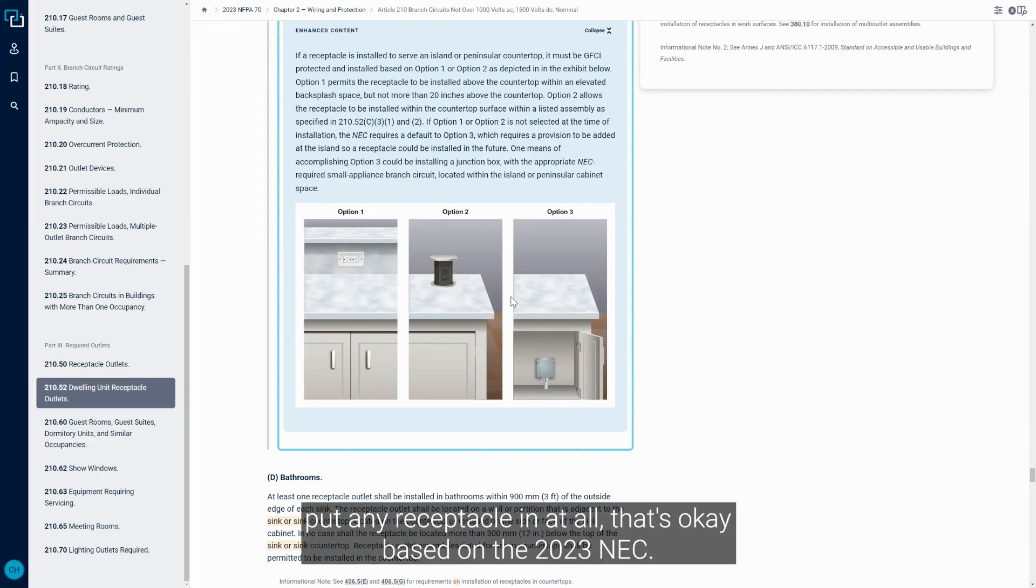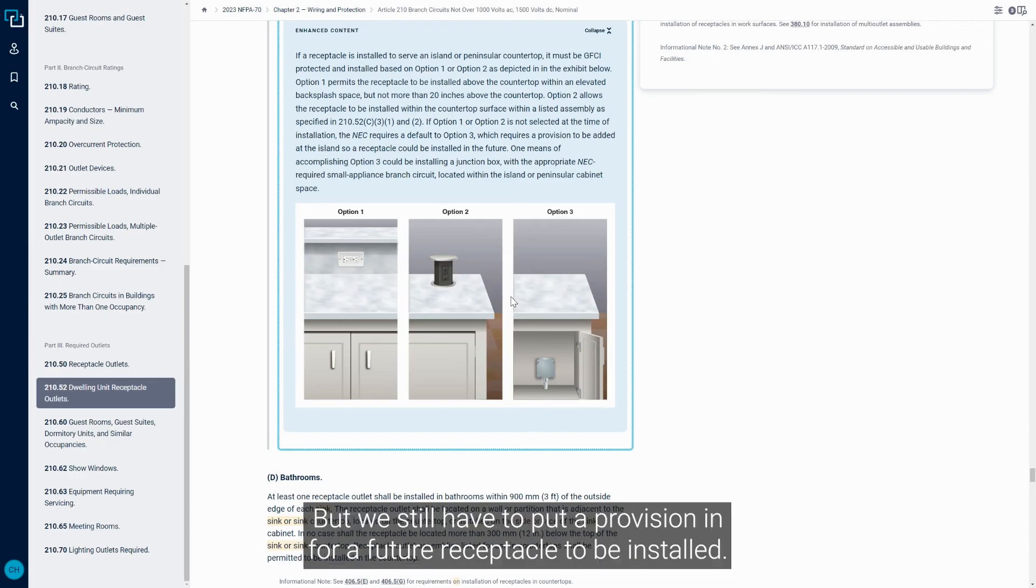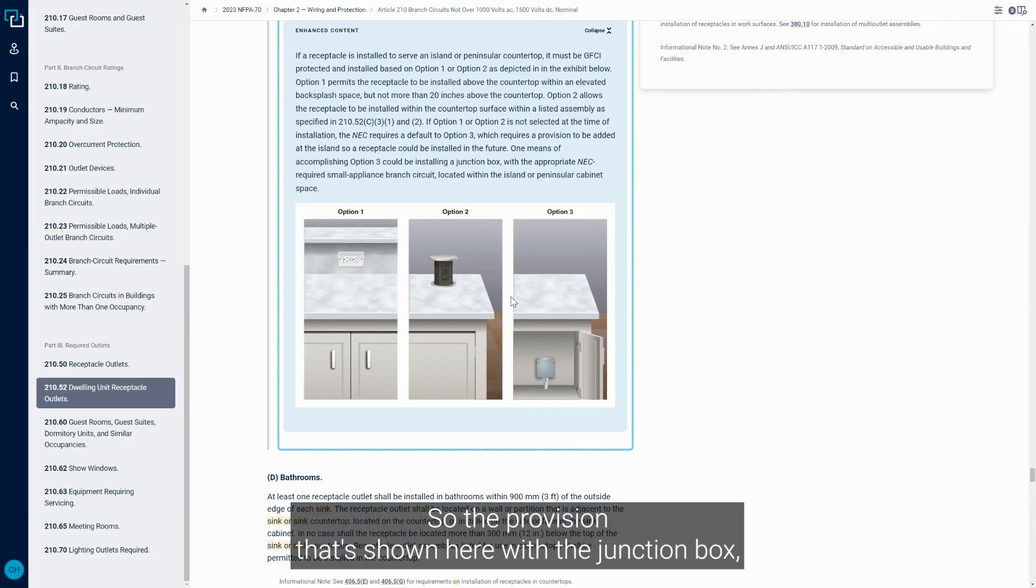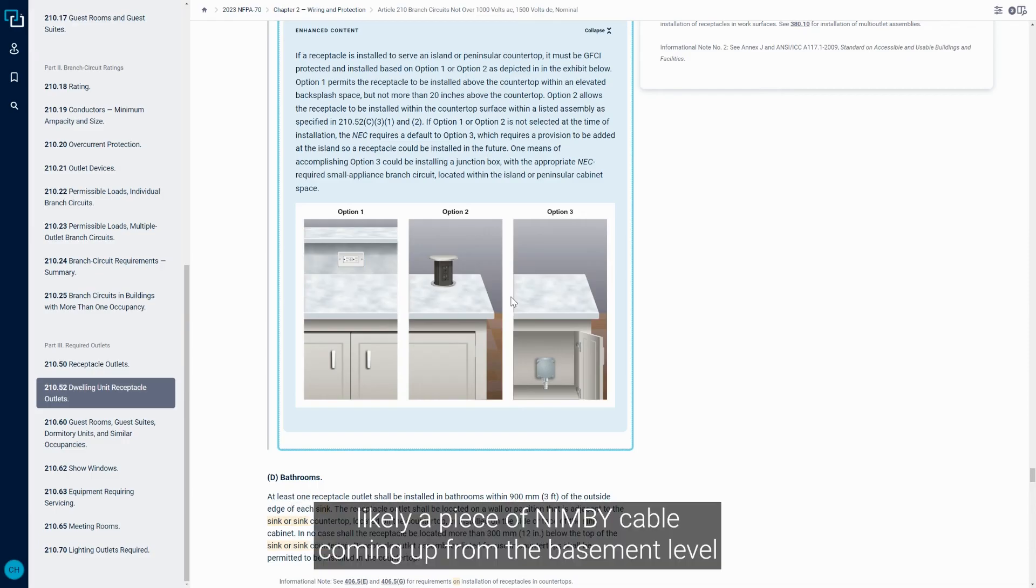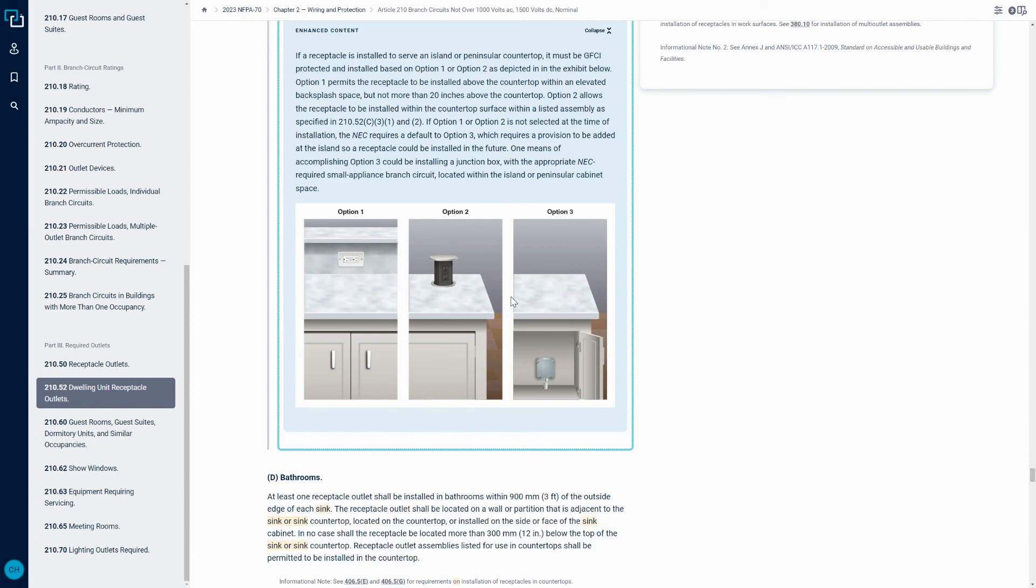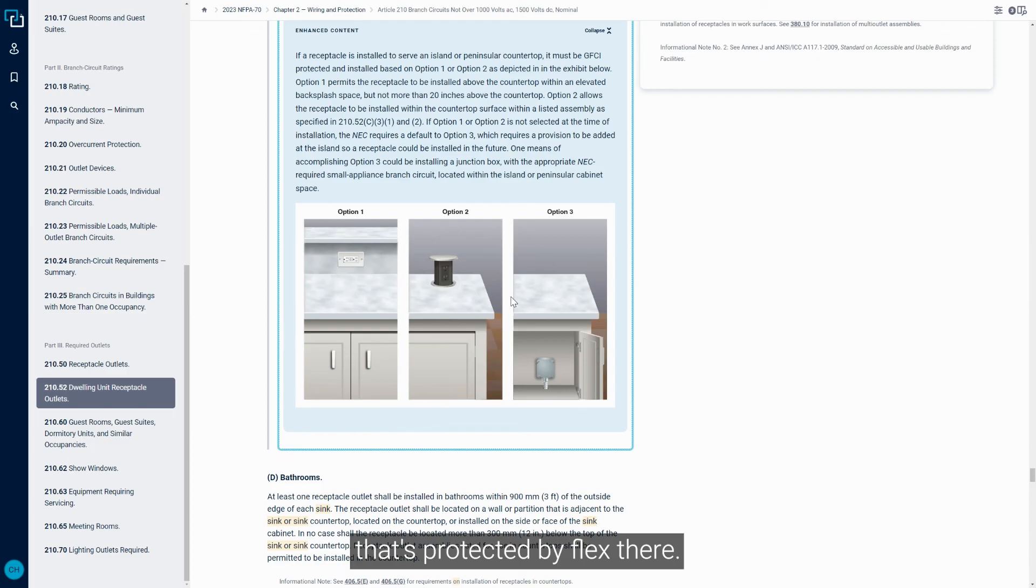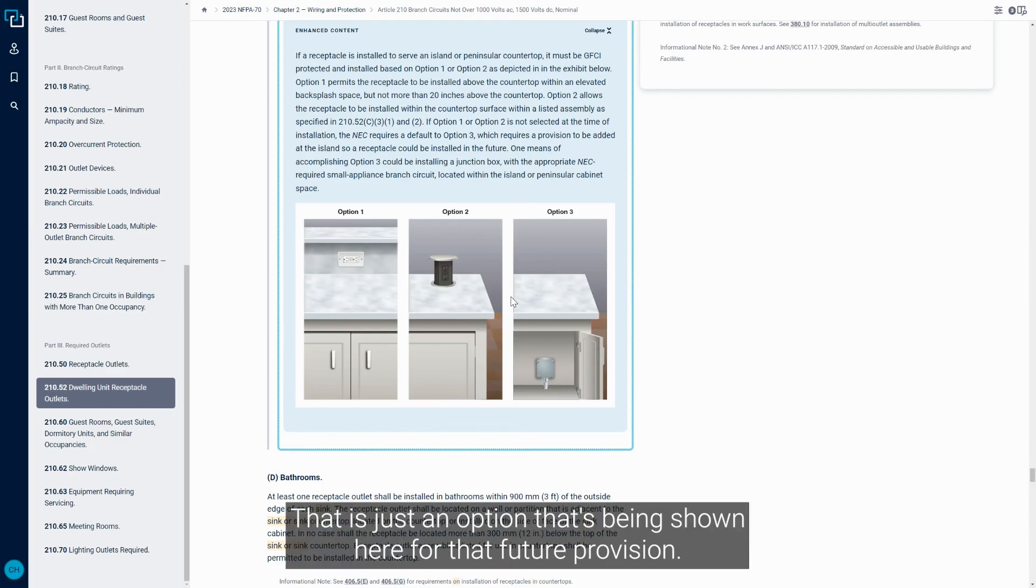And if we don't put any Receptacle in at all, that's okay based on the 2023 NEC, but we still have to put a provision in for a future Receptacle to be installed. So the provision that's shown here with the junction box, likely a piece of NMB cable coming up from the basement level that's protected by flex there, that is just an option that's being shown here for that future provision.